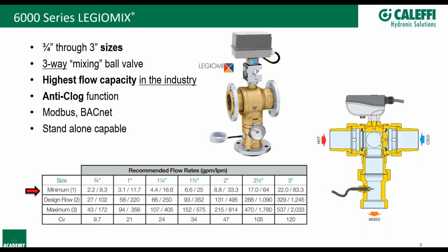So if, say, you desire to have 120 distribution temperature, but your tank is 120, on a thermostatic mixing valve application you're still going to have some cold coming into the distribution. So your 120 tank is going to get mixed down to 115 or 110 or 105 or somewhere lower than what you desire it to be. The idea with the ball valve is that it can completely close off the cold side if it needs to. During normal operation, you definitely want to have some differential there so you can get good control through the valve. But if it does come down to it and your tank really gets drawn down quite a bit, like I said, it can completely close off the cold side and send 120 right from the tank out to the fixtures, no problem.